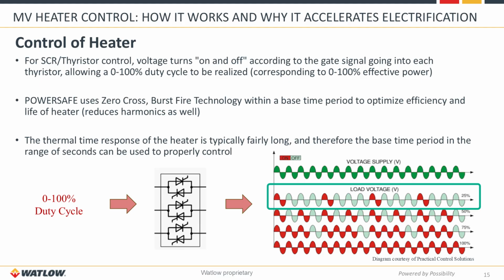like you would see in some of the traditional pulse width modulated systems. Rather, we burst fire this, and by burst firing, I mean we're turning on and off the waves throughout the period so that you level the load throughout that period. If the total time period were the length of this graph right here, you're basically getting 4 bursts within that 25% duty cycle. This ensures that you're spaced apart enough to keep the element temperatures as constant as possible while still only giving 25% of the wattage output into the system.